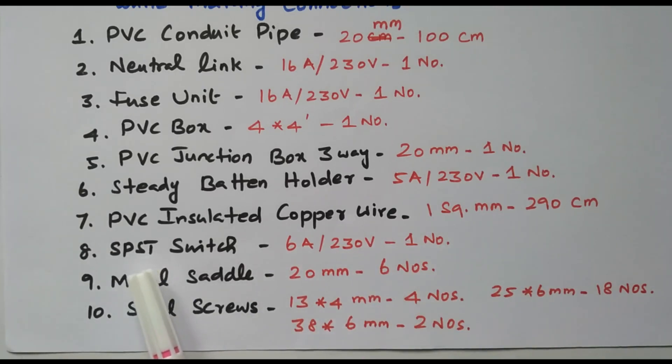Single pole, single throw — only the phase is controlled. Single throw means on or off. Metal saddles, 20 millimeter, 6 numbers required. Steel screws: 13 by 4 millimeter — 4 numbers; 25 by 6 millimeter — 18 numbers; 38 by 6 millimeter — 2 numbers. These are all the requirements and materials needed for doing this wiring of two bulbs connected in series controlled by one single switch.